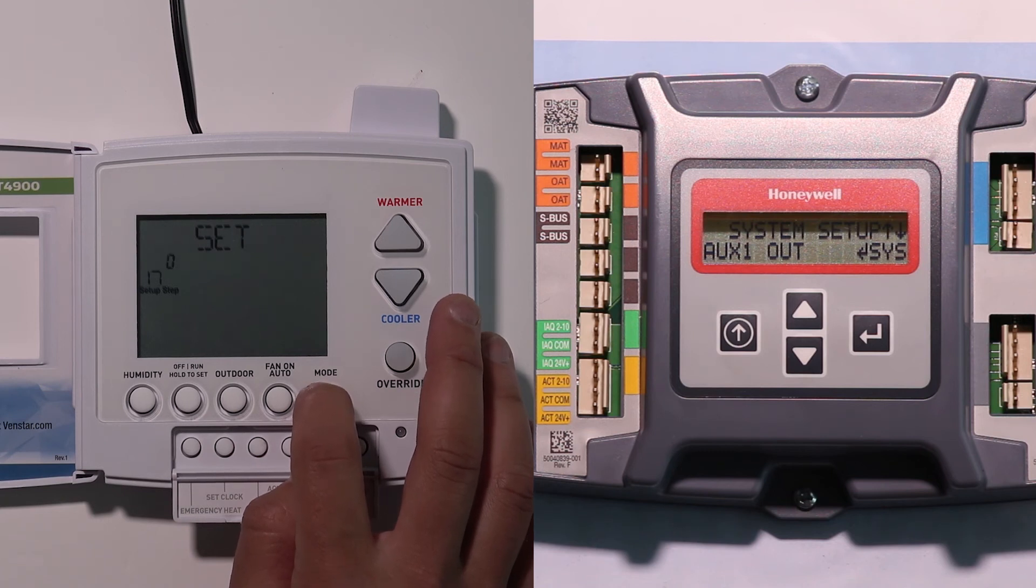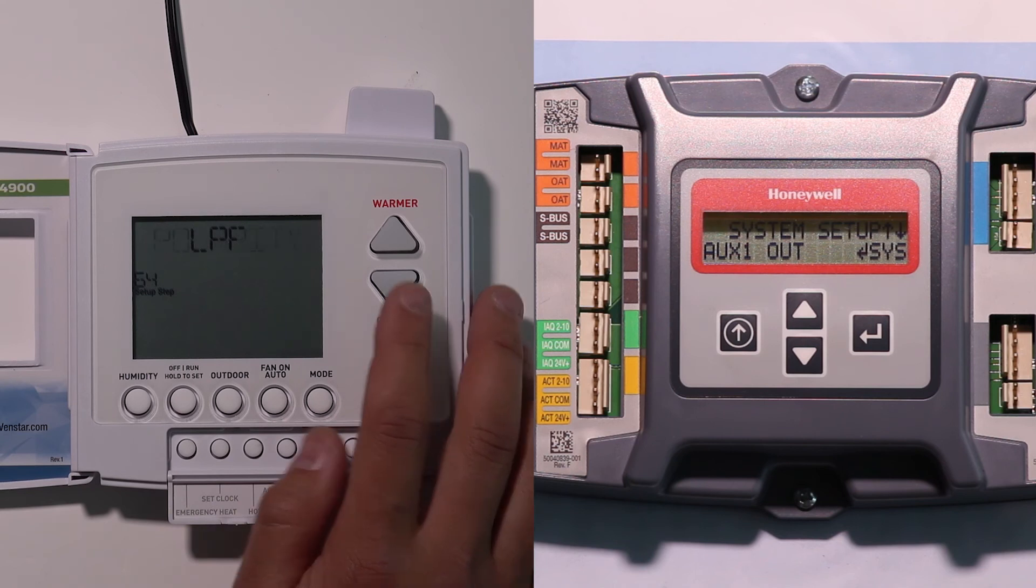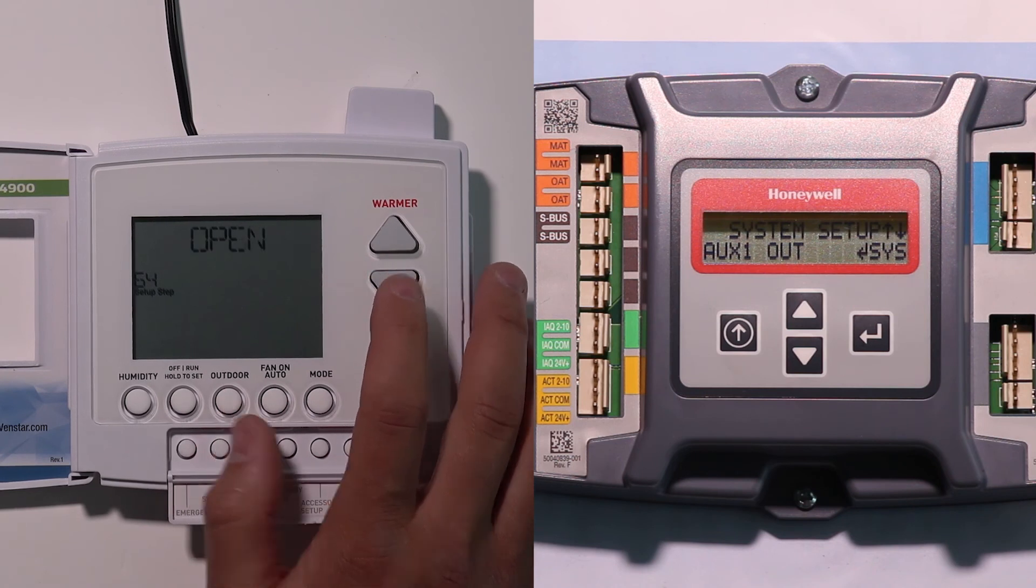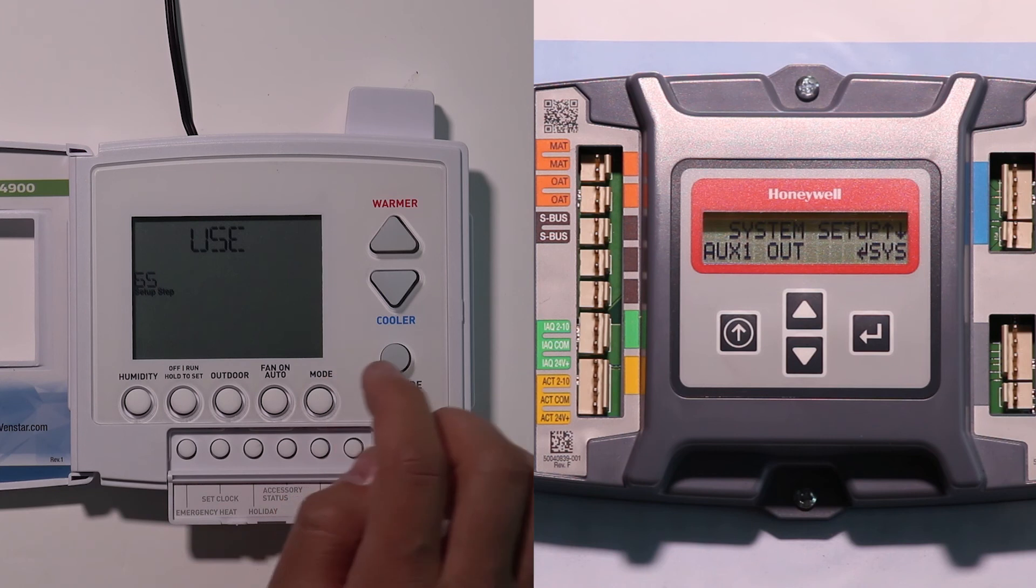And in this case, I want to get up to settings 64 and 65. So on setting 64, that tells me what my contact is going to be. I want it to be normally open. So that's what it is right now. If it wasn't, I can change it by hitting the up and down arrows between open and close. So I want normally open.